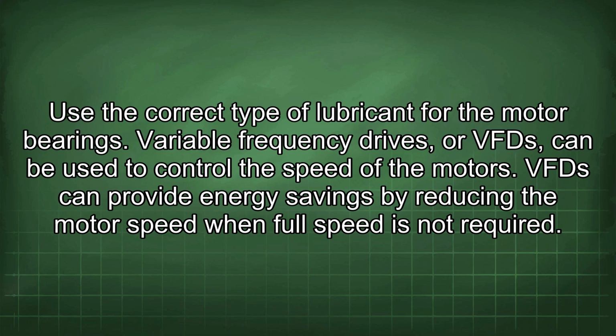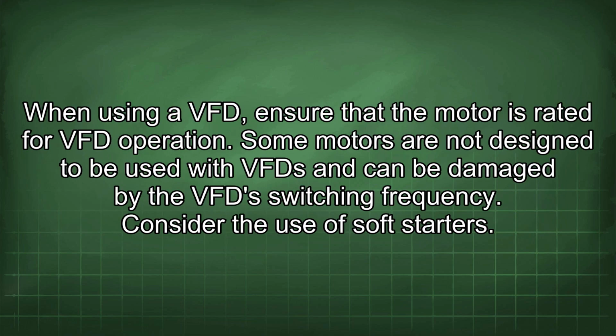Variable frequency drives, or VFDs, can be used to control the speed of the motors. VFDs can provide energy savings by reducing the motor speed when full speed is not required. When using a VFD, ensure that the motor is rated for VFD operation. Some motors are not designed to be used with VFDs and can be damaged by the VFD switching frequency.